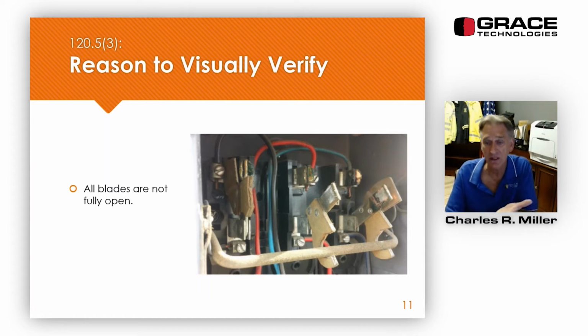Now, with a regular circuit breaker, even if we have the panel cover off and we turn off the breaker, can you tell that the contacts are separated in a regular circuit breaker? No, you can't tell that. So this is the reason it says wherever possible. If it is possible, visually verify.